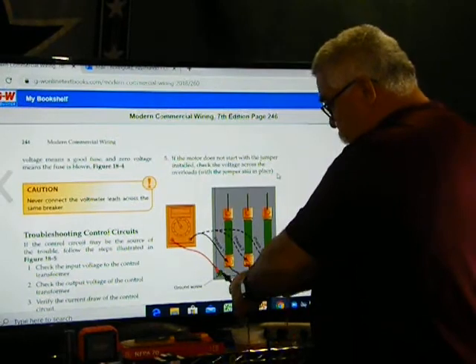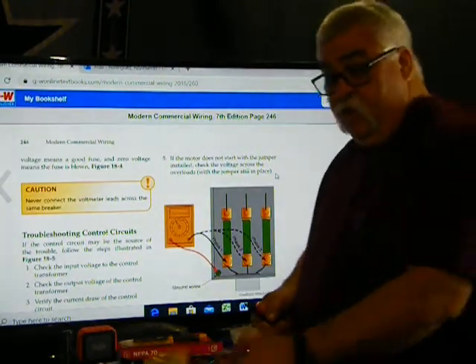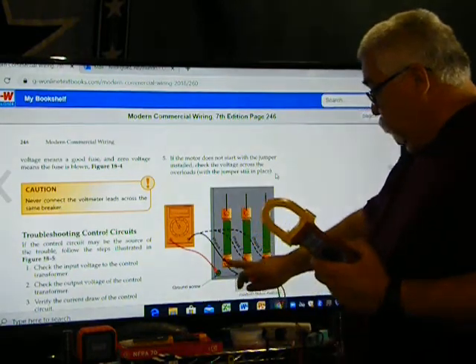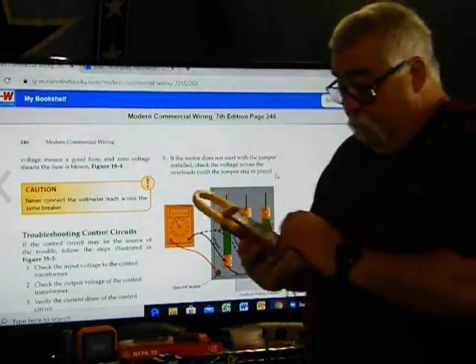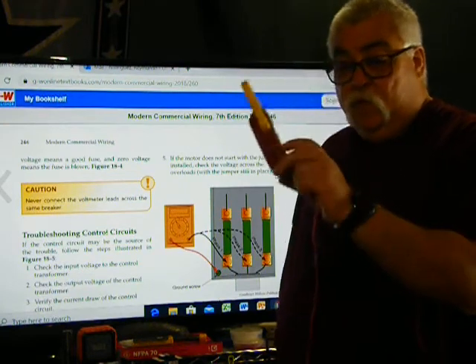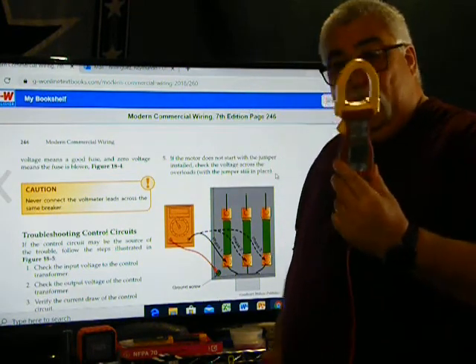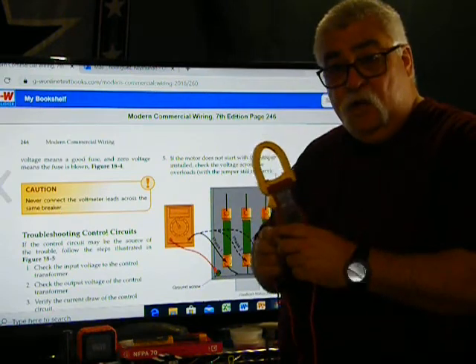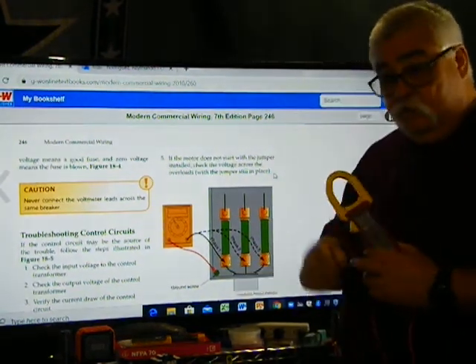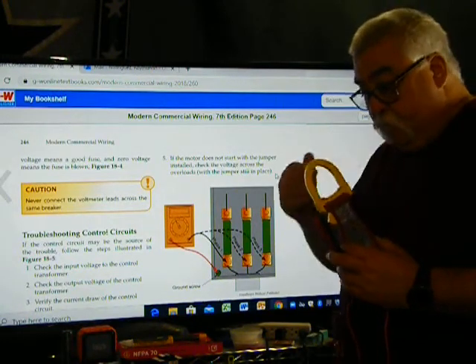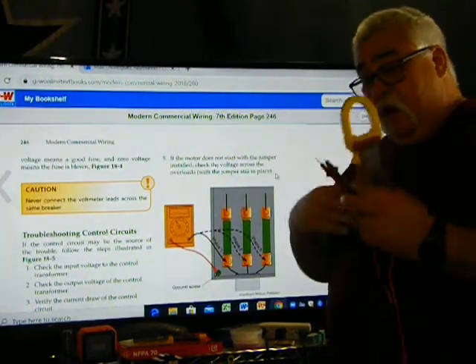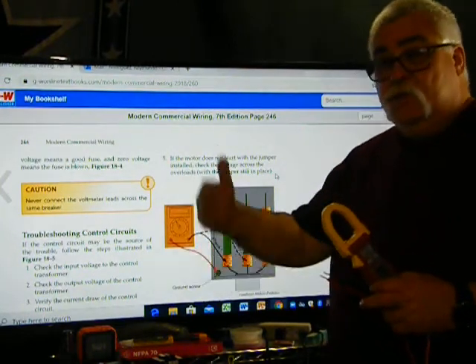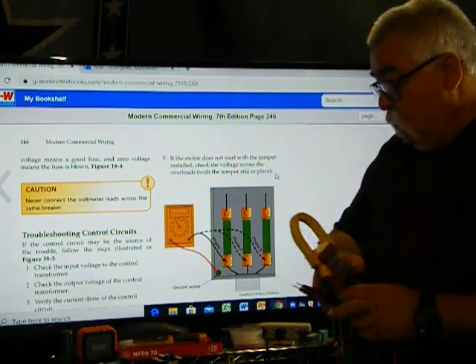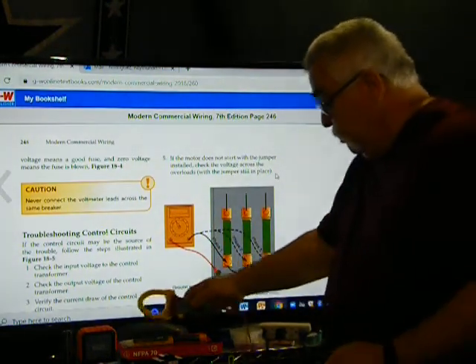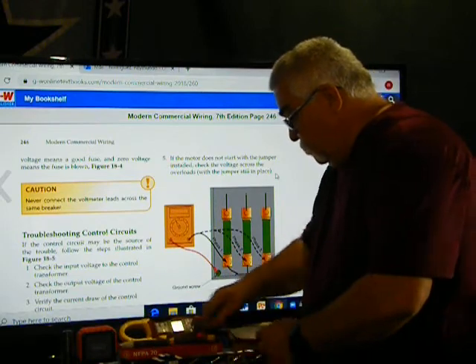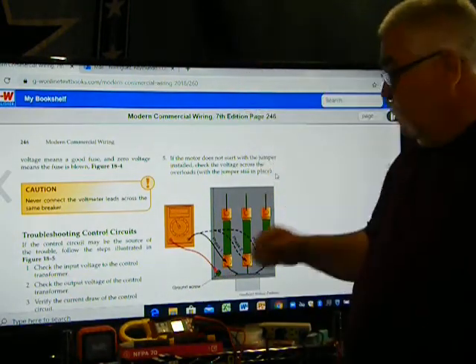And then you would go to the ground and touch each one. Guess what? Anytime you go from the ground to a hot with the power off, your tester should say OL. Just like this one says OL, open line. Okay, if you start getting numbers in here between the ground and one of these hots, there's a problem. Okay, that's one thing that I didn't observe. I didn't go through that step because I took somebody else's work. Okay, just referring again, now that I got a tester and I got a disconnect up here so I can show you. Always when you're testing the motor, okay, turn power off and check resistance.